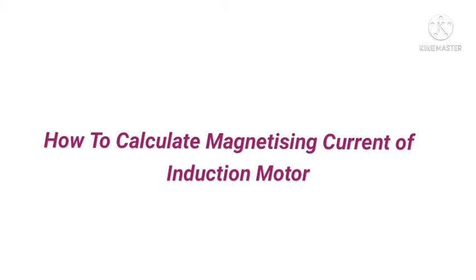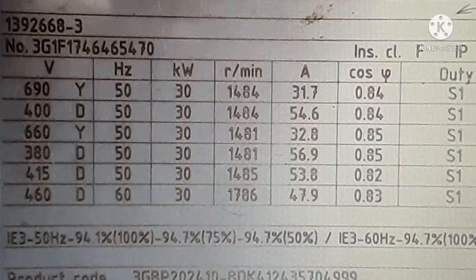Without this magnetizing component, or without establishing the magnetic flux inside the motor, it's not possible to transform power. So the magnetizing component is also of great importance inside the motor. Today I will consider a real nameplate of a motor and will show you how we can calculate the magnetizing current.